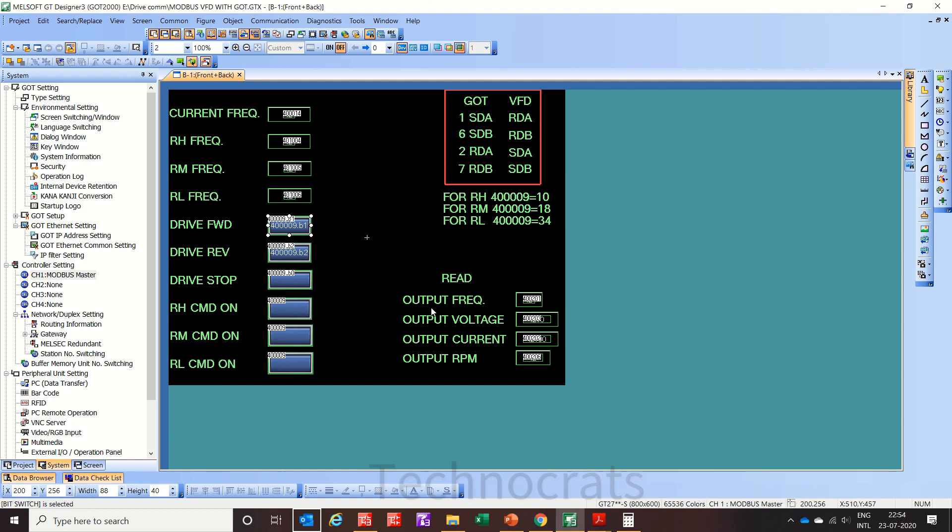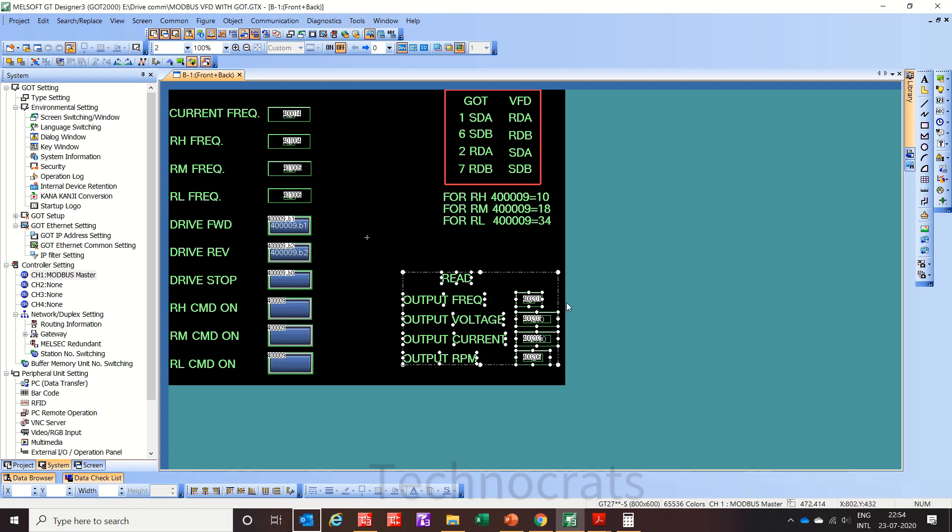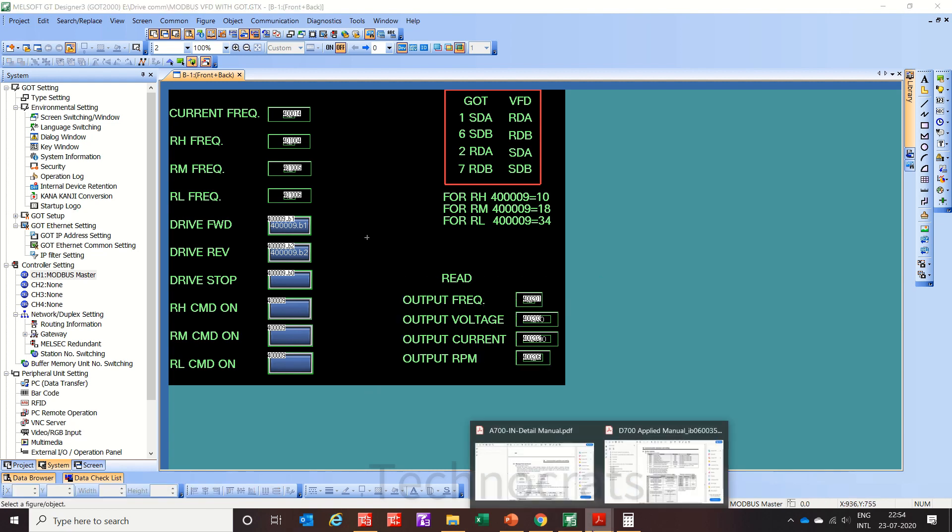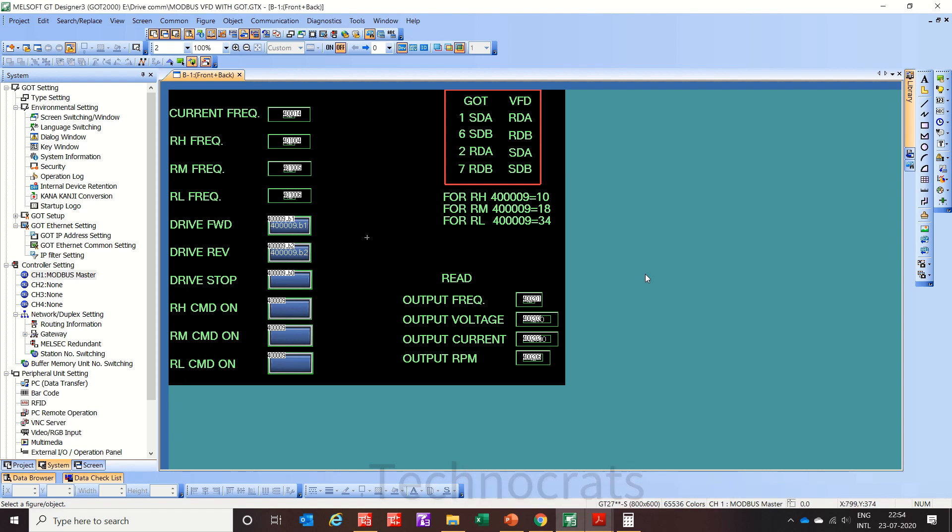Now output frequency, you can read here output voltage, output current, output RPM, you can all read as shown in Modbus addresses. So you can use any of the Modbus address as per your application to run this VFD using HMI.